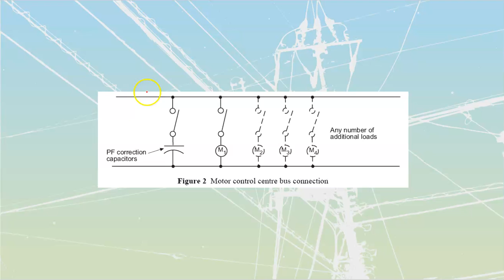In some cases, correction is already applied, so it's not us doing the power factor correction. If you look at lighting ballasts, any inductive type ballast will often have that lagging power factor. They'll have a cap inside them to correct it, and they'll usually note that on there.